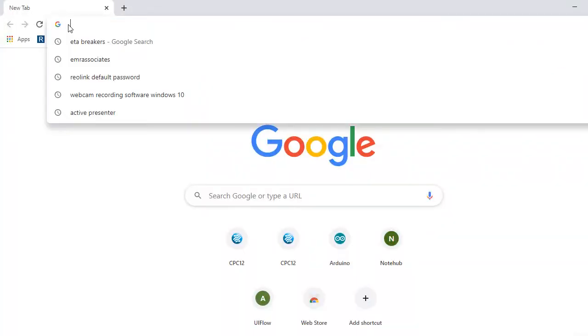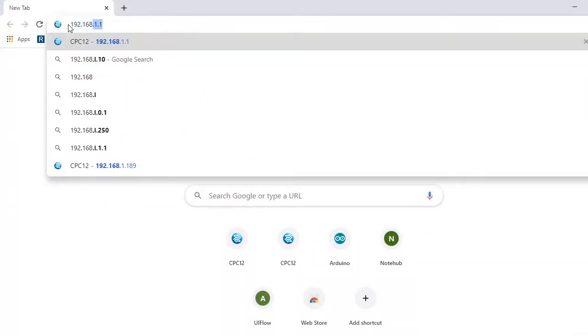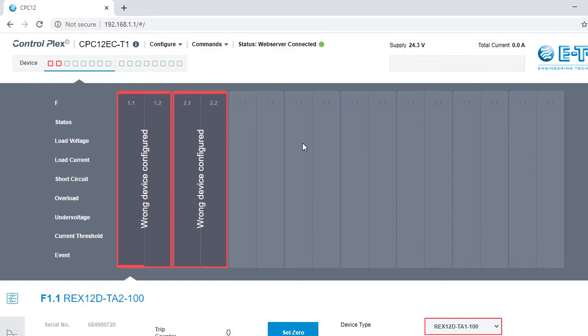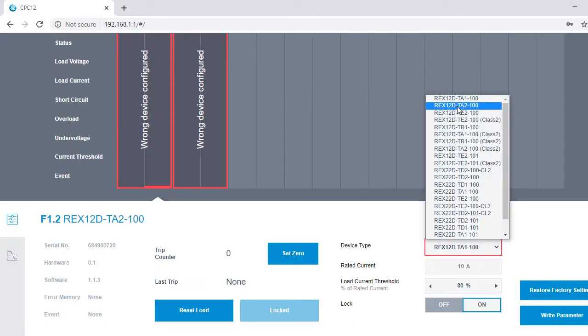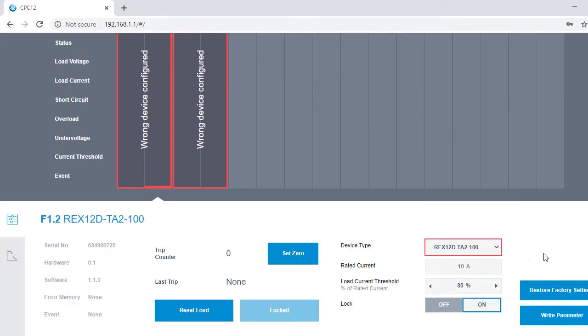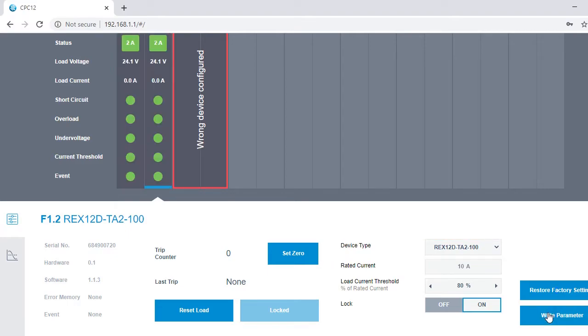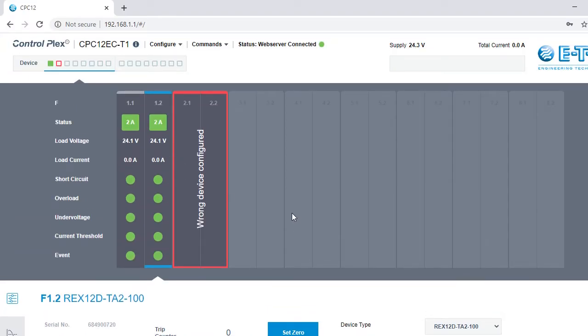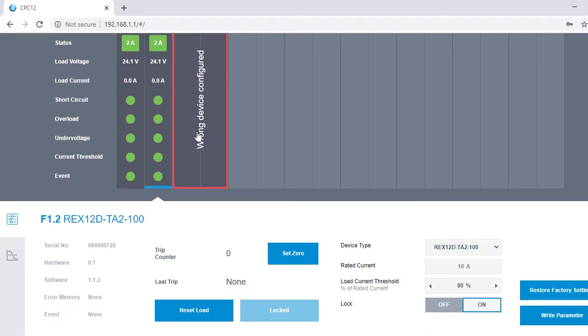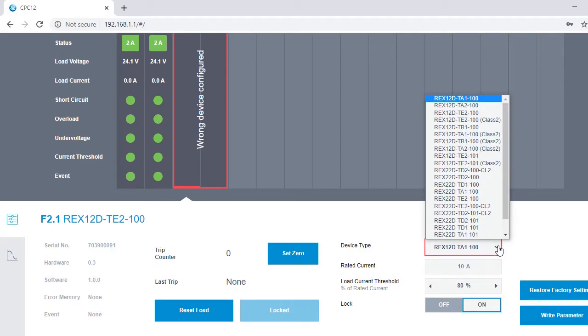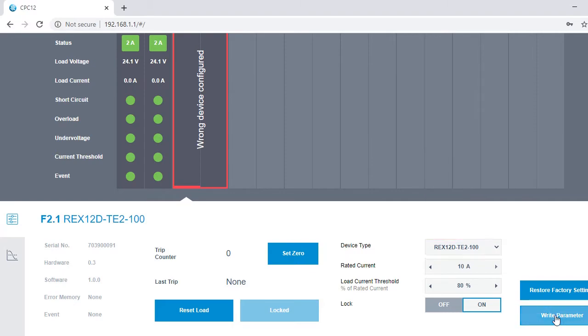Now that our hardware is done, we'll type in the default IP address, 192.168.1.1. It'll bring up the internal web server of the CPC-12, and you can see we will configure the actual breakers now. So we tell it what's in the slot, it will discover it, automatically set the current for that breaker, and give us a status of both amperage and voltage coming from the breakers once they are configured.